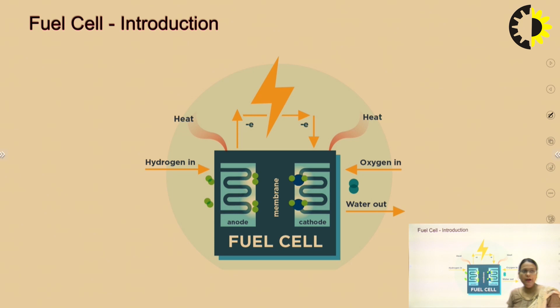First of all, it has a very high efficiency, around 70%, because it involves a direct conversion process and does not involve any thermal process, right? It also uses fewer mechanical components, so maintenance is obviously very less, and fuel cells take very little time to start operation. As soon as we provide hydrogen and oxygen to the anode and cathode, the process will start. The space required by a fuel cell power plant is also very less, and a large amount of cooling water is not required, unlike in a conventional steam power plant. Wherever it is required, we can install the fuel cell near the point of location, as it requires very little space, and the best advantage is that it does not make any kind of noise, so it can also be used in residential areas.